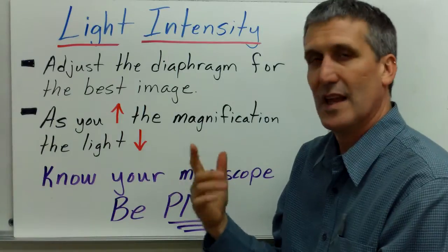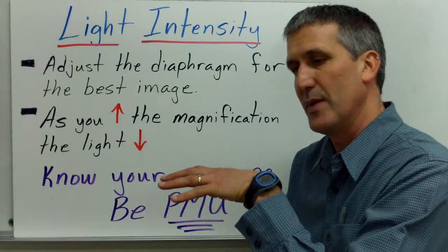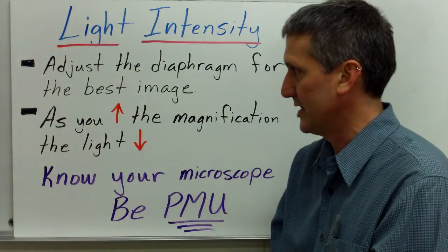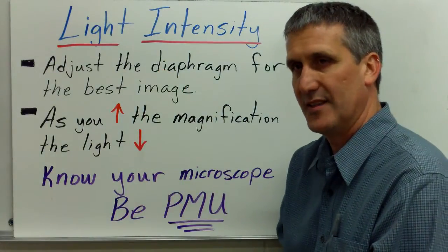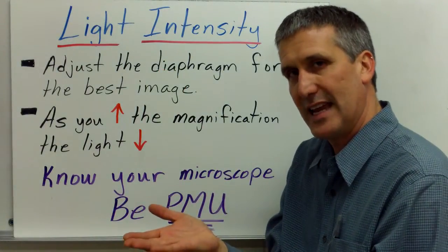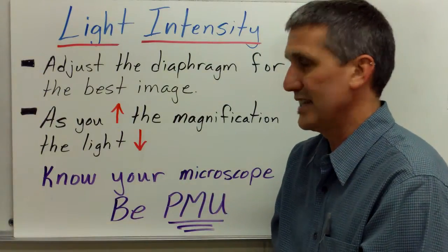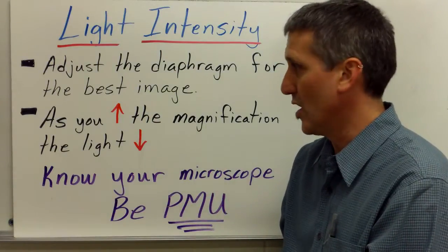Another thing you need to keep in mind is light intensity. It's a compound light microscope. The image is formed by the light passing through the specimen and then being magnified by the lenses. So, you always want to be checking and adjusting the diaphragm, which is underneath the stage, to see how much light is passing through the specimen. Because if there's too much light, it could be washed out. If there's too little light, the image may be too dark.